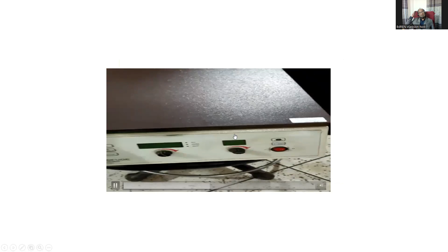So our engineer investigates the power supply program. We go through another issue where we connect and fix the fuse, and also check the primary voltage of the transformer and the secondary voltage of the transformer. This power supply depends on the conventional machine, so we need to check the rectifier to ensure the power voltage is okay or not.